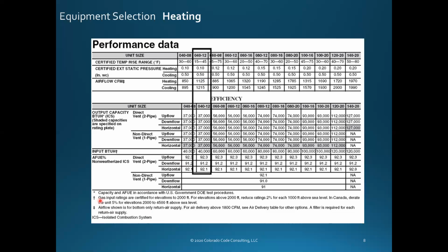So here, gas input ratings are certified up to 2,000 feet. Very, very typical. For anything above 2,000 feet, it says reduce ratings 2% for each 1,000 feet above sea level. Since this particular example was in Denver, I did 5, right? 5,000 feet. 5 times 2 is 10. Take it times 0.9 and we're good. Never understood why in Canada it's different. No idea what's going on in there. Different test standards, perhaps. Don't know.